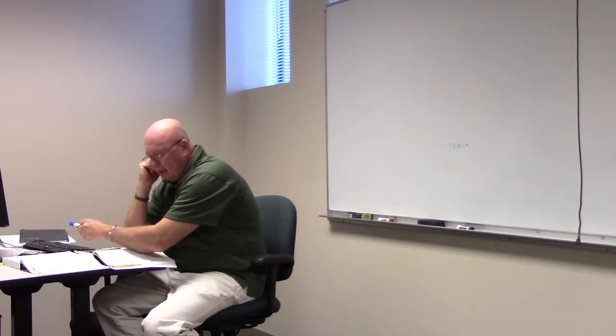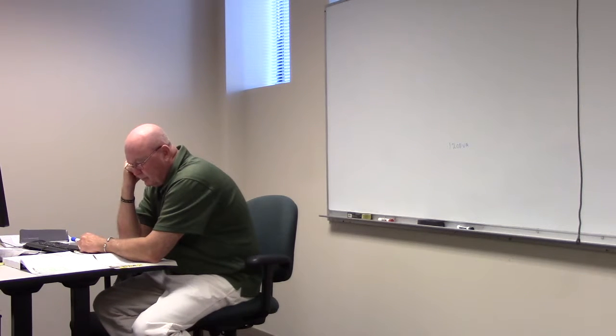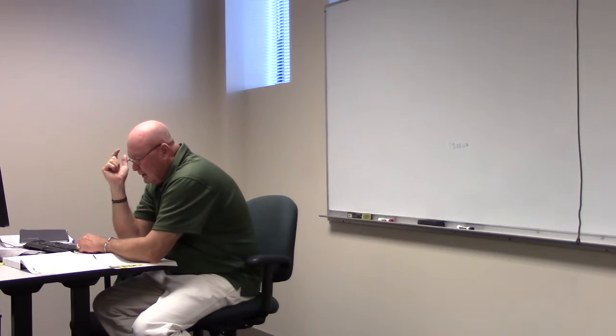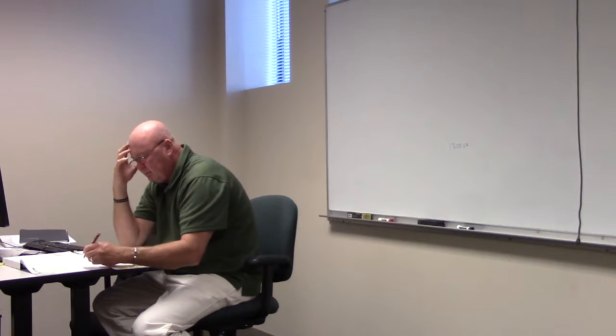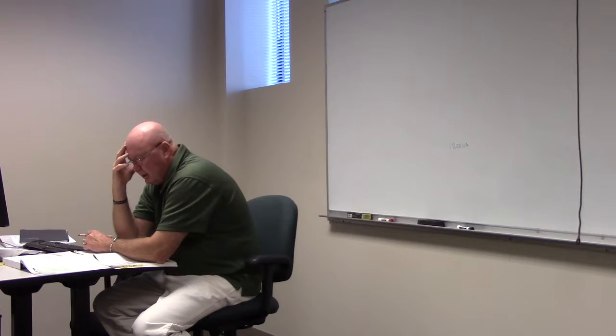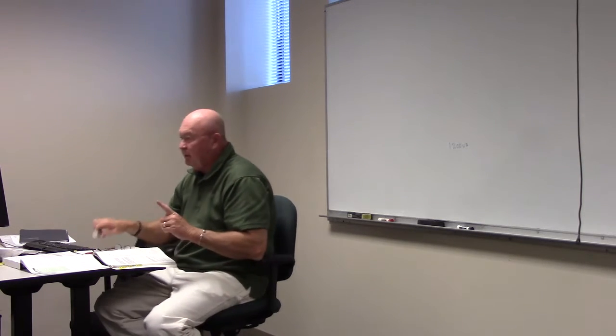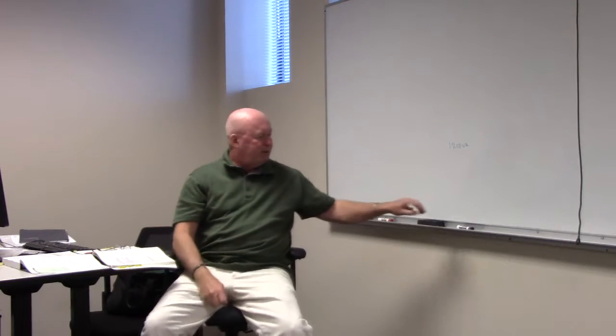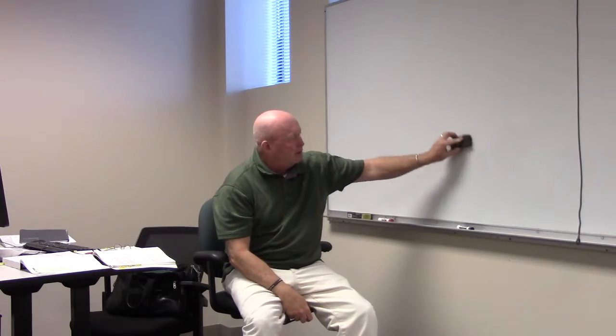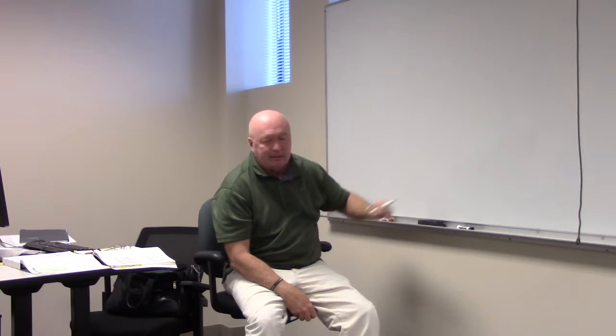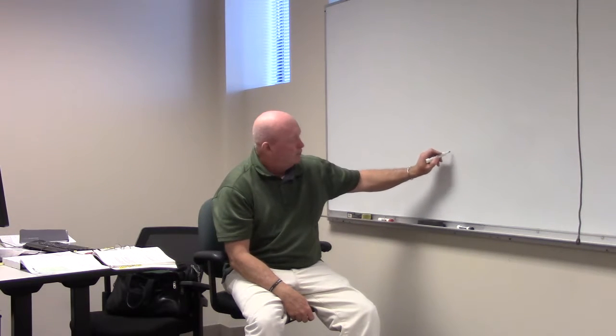So reading on down there on page 28, we see that it talks about commercial occupancy should be considered continuous, and I'd probably underline that, unless specific information is given. So in a commercial facility, they're saying it should be considered continuous unless contrary. Now, if a load is continuous, what is the one thing we know that we have to do to a continuous load? We have to multiply it times how much percent? 3. No.